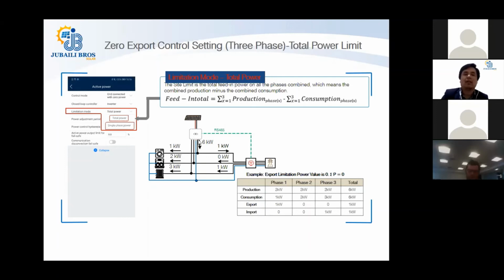Since the inverter cannot give variable output per phase, it will distribute the 6 kilowatt to each phase, 2, 2, 2. In the first phase, there will be 1 kilowatt going towards the grid. In the second phase, there would be zero power going to or coming from the grid because it matches the load requirement. In the third phase, it is a 3 kilowatt load and the generation is only 2 kilowatts, so 1 kilowatt will be taken from the grid. But if you sum the power going towards the grid and the power coming from the grid side, it is actually zero. This is the type of control you can do if you need, and for that, under the limitation mode, you will have to select the total power.